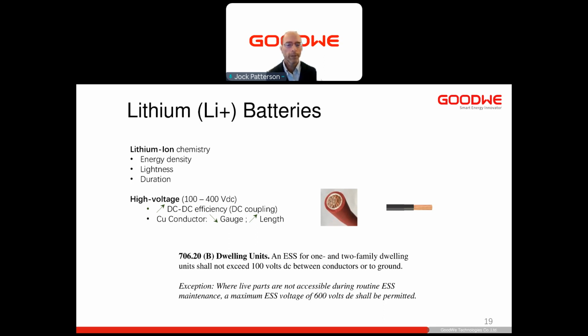And instead of needing the big red 4-aught cable that you see here, you can use the smaller black building wire, maybe a number 6 gauge, simply because we're at higher voltage. So that saves you on copper costs and dealing with bulky cables. You can also run longer lengths, so your battery doesn't have to be next to your inverter. For example, your battery might need to be in the garage for environmental reasons, right? It gets too cold outside or too hot, but your inverter can put up with that temperature swing. So you put your inverter outdoors and your battery indoors, and you do not have to deal with thick cables running through walls, just simple building wire.